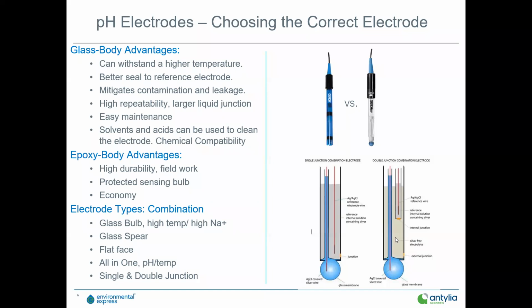As those poisoning ions can get into the electrolyte, obviously they're big. The metals are big and positively charged. That'll attack the chloride part of the reference tip. The phosphates, sulfates, nitrates are big and negatively charged. That'll pull off the silver ions. So what happens is these poisoning ions work their way through the electrolyte and will try to attack the reference tip. The double junction actually has, we've got a couple designs with the glass capillary tube. Normally they're not on the lower side, it's actually on the upper side of this capillary tube. And the poisoning ions have to go all the way up and around back to get to the reference.